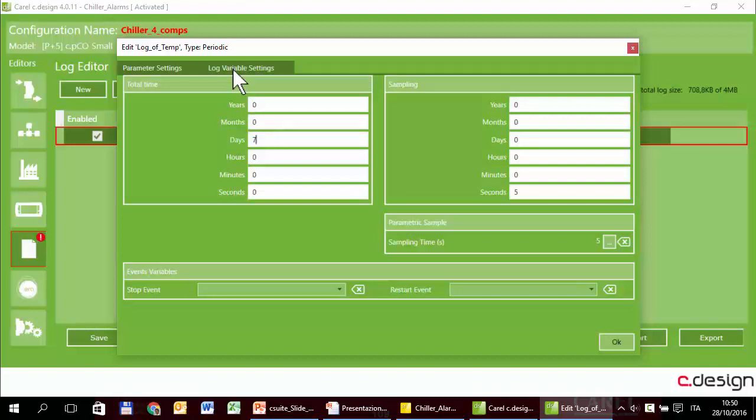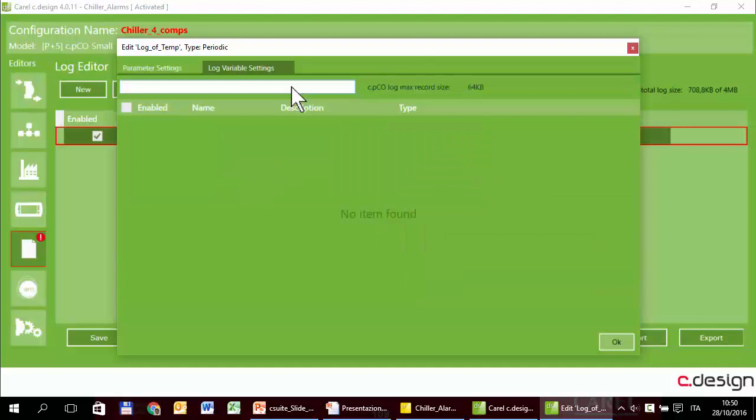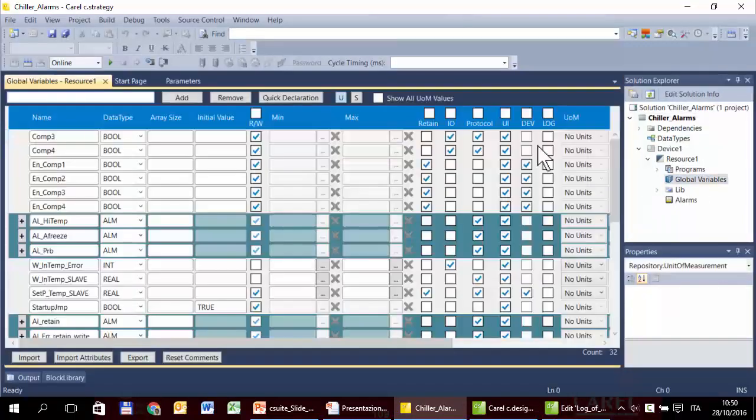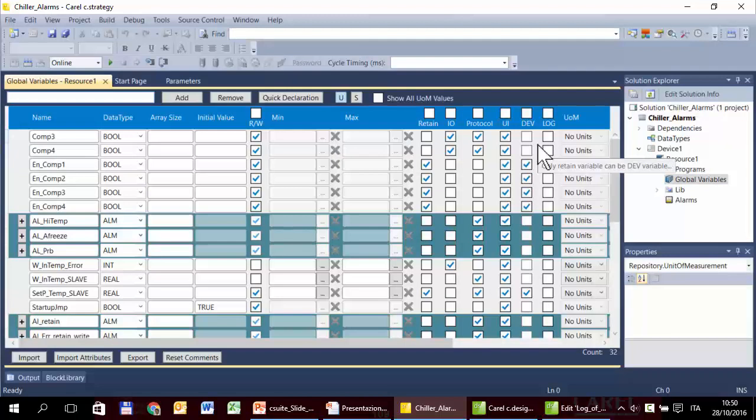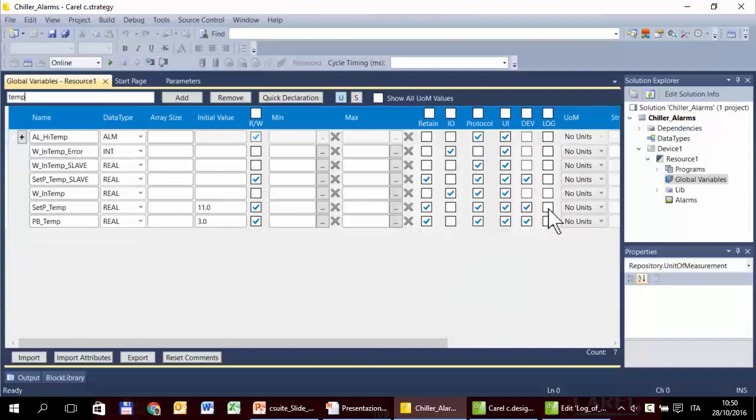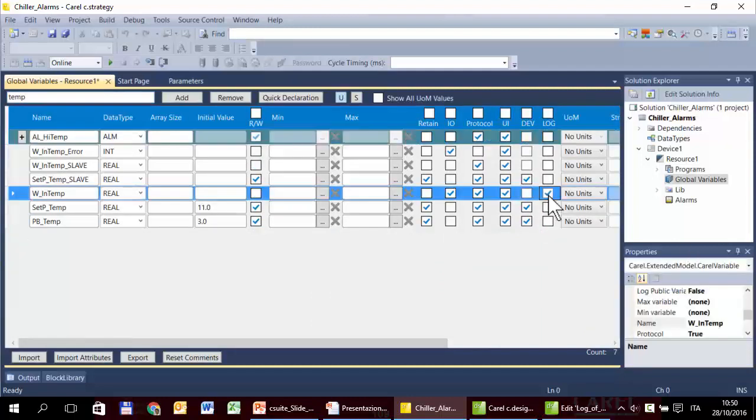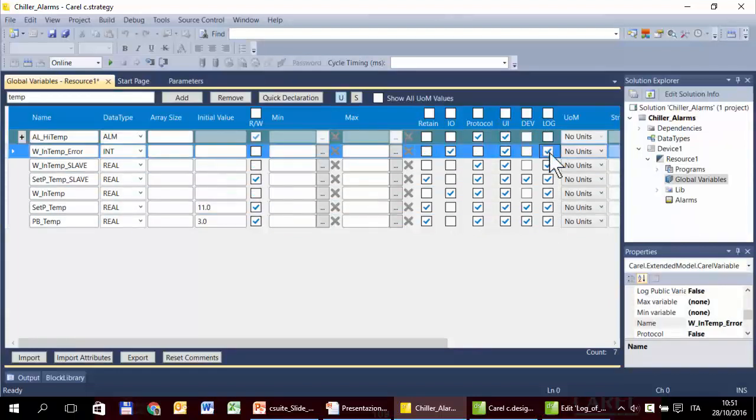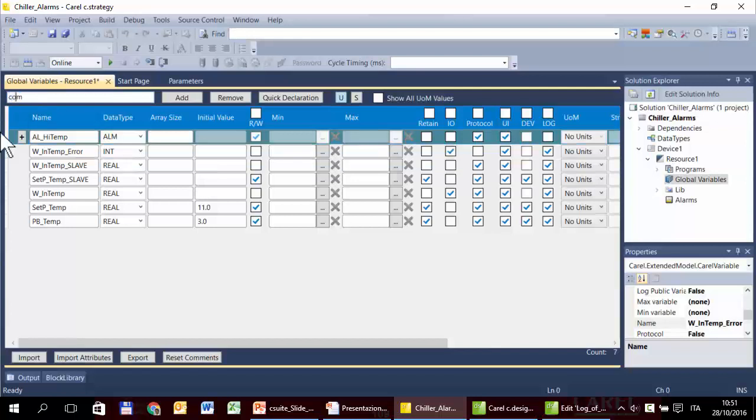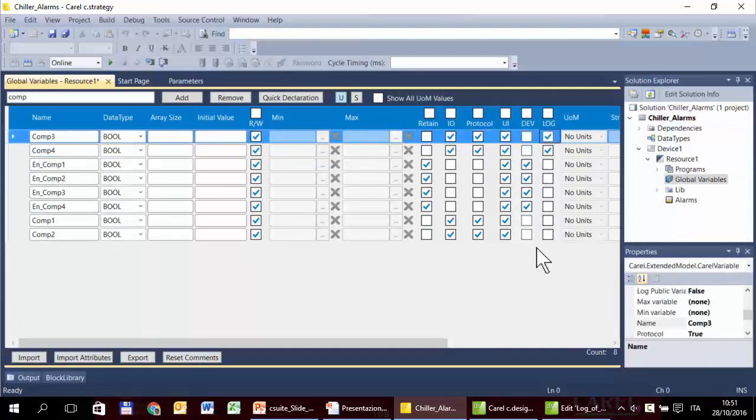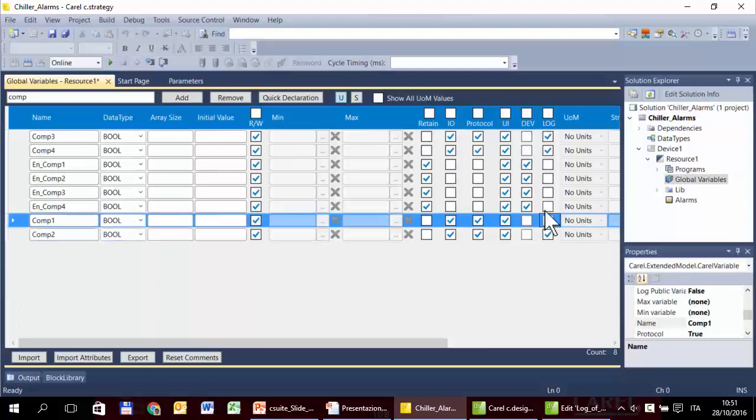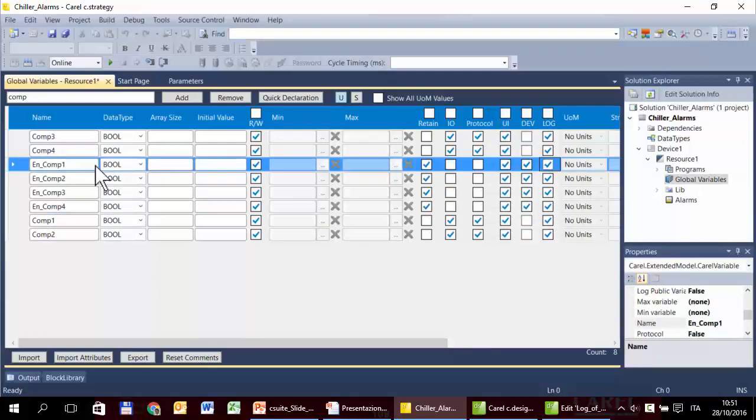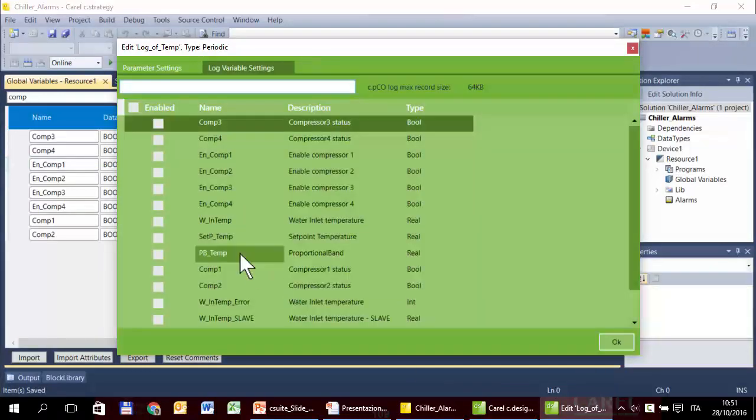In the next tab we can select the variables we want to log. So there are no variables. Why? As usual, only the variables that have the corresponding flag here are visible in the corresponding editor. So to see variables in the log editor we have to set this flag. So we can select some variables. In this case we need just the temperature, but I select some other variables just to have some more in the editor, and also the compressors because later we need them. Remember to save in order to see the variables.